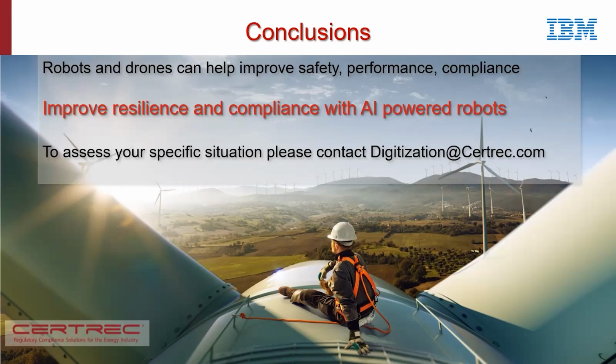That's great. By the way, we have one more question from Alex. What are some use cases for Spot at substations? Absolutely. One of the biggest use cases at a substation that we've been working with utility on is thermal imaging. We started with hinges, clips, and switches, and now we'll be moving forward to transformers, and I forget a couple other kinds of assets, but there are many different kinds of assets.